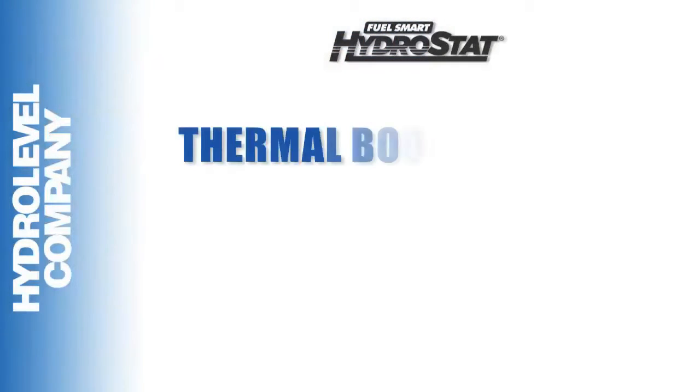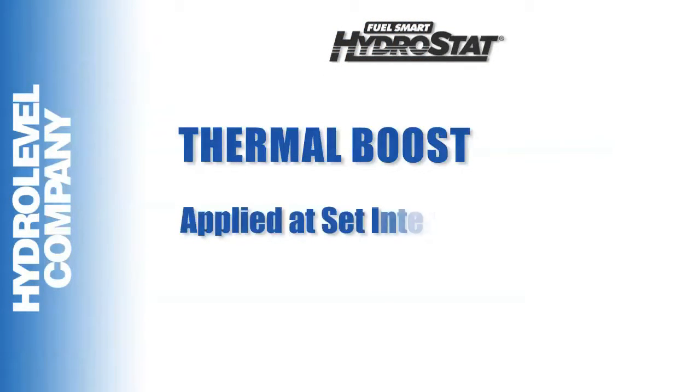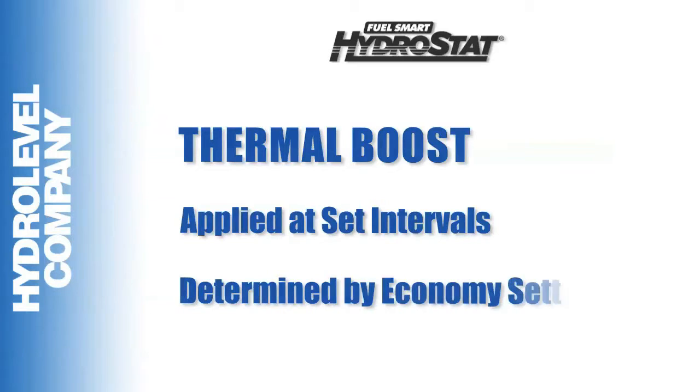When the demand is great, such as a steep incline, extra engine power will be needed, so the cruise control will apply more throttle. Thermal targeting is similar technology whereby the hydrostat will try to satisfy the heat demand at the lower water temperature. If the demand cannot be satisfied within a specified time, the thermal targeting boost feature will raise the water temperature. Thermal boost is automatically applied at set intervals determined by the economy setting.